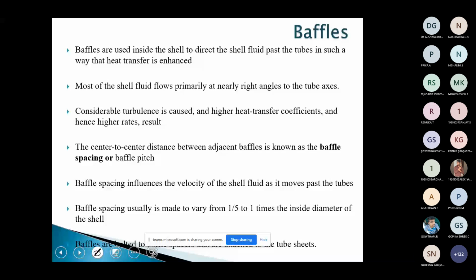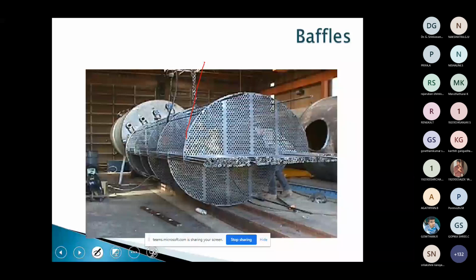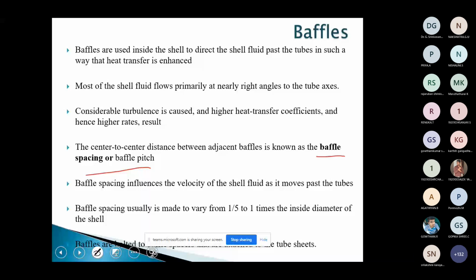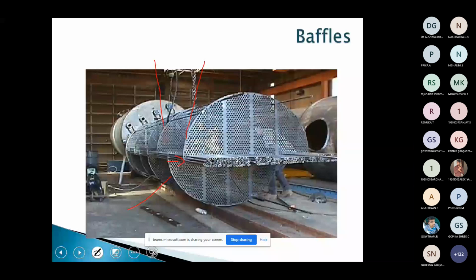One important term we will be using is baffle spacing or baffle pitch. You can see this is the baffle, this is the second baffle, this is the third baffle. Actually it is in semicircle form, it is cut. Baffle spacing or baffle pitch is nothing but the distance between two adjacent baffles, center to center. And this cut is called the baffle cut.